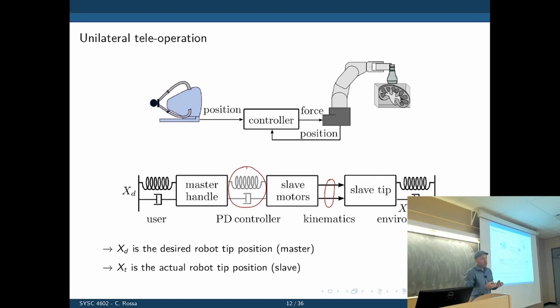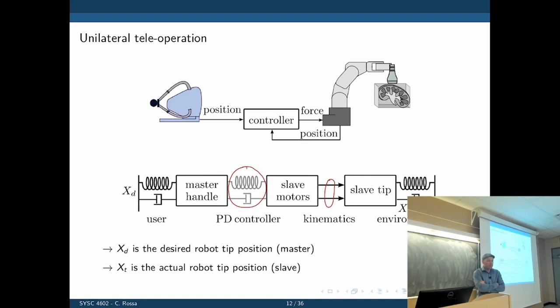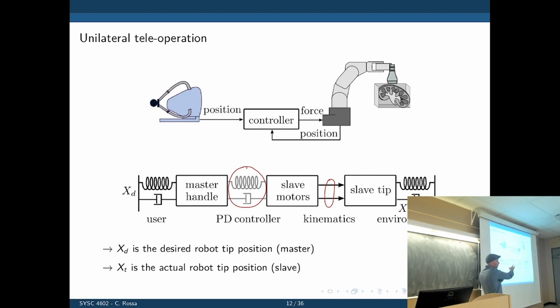The implication is that you are now controlling an environment without any sense of touch and without any feedback. That's how all commercial surgical consoles work today. One research area in the lab is finding ways to restore this haptic feedback — through redesigning the control scheme, or by adding new actuators and sensors at the slave environment to measure the interaction between the robot and the tissue, and then restoring that to the user.